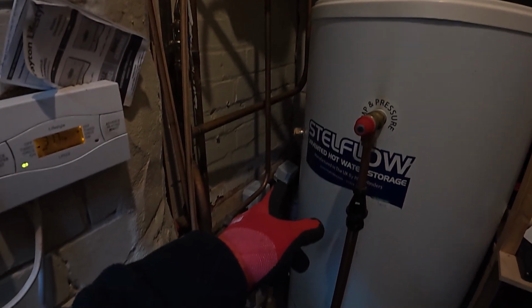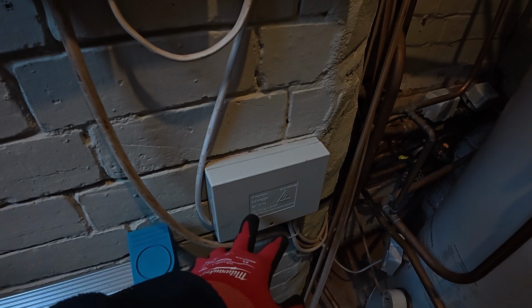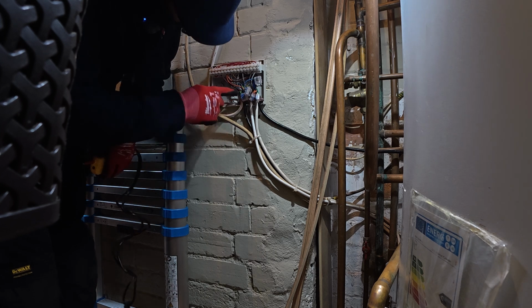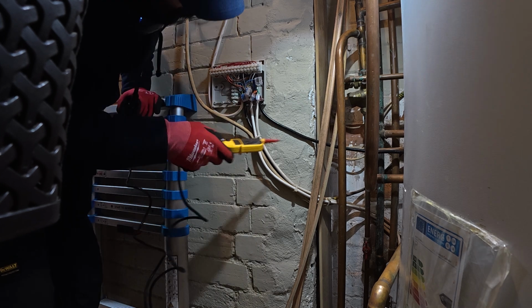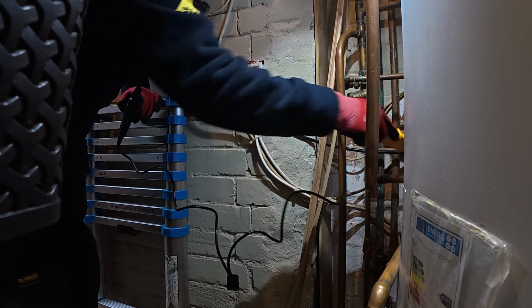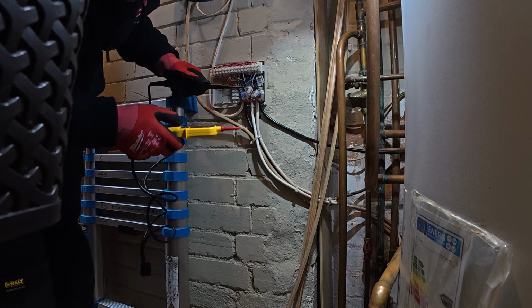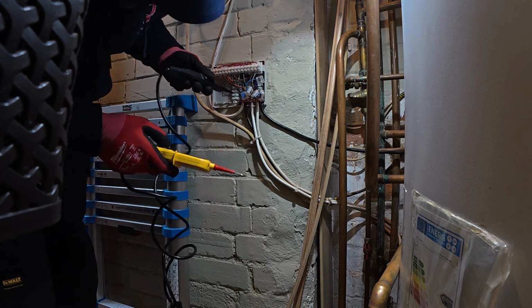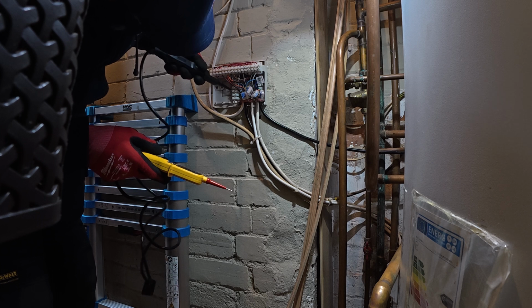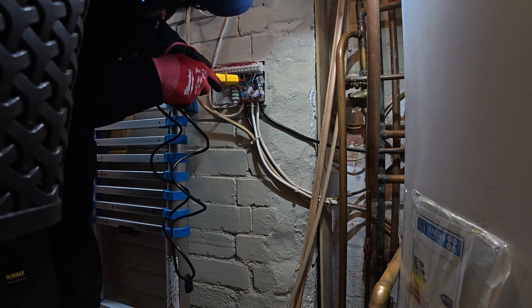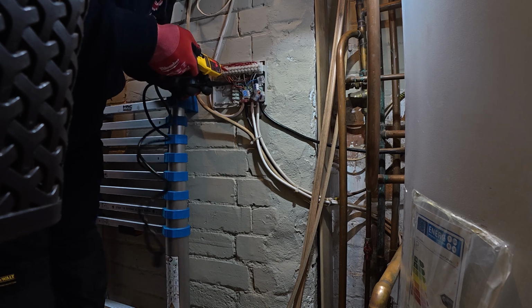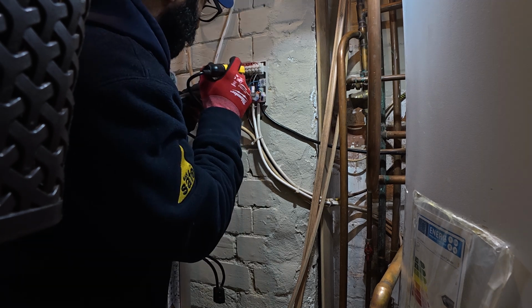So I'm going to basically now check the wiring centre over here, how far the power is getting down the circuit, and see where the fault lies. So we know here is our programmer cable. This is easy to work back from, this cable, this one here. Let's have a look where the break is. So that's onto a neutral. Is that a neutral or an earth? That's an earth. I've got neutral to permanent live, which should be 230. That's permanent live.